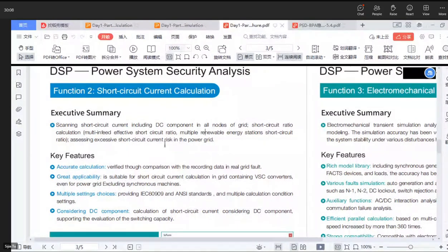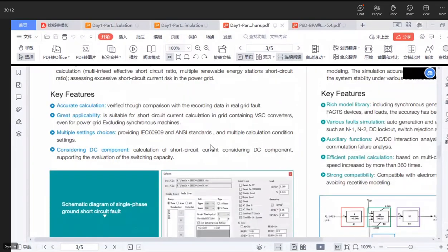The key feature is accurate calculation with great applicability. It is suitable for short circuit current calculation in a grid containing VSC converters, even for power grids excluding the generator, because the VSC converter will provide the short circuit current during the fault.